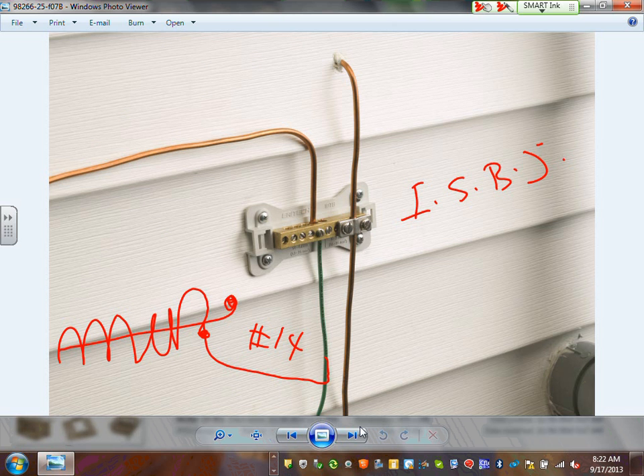It has a space where you can bond the shield. Then you take number 6, and that goes all the way to a ground rod or to the grounding electrode system of your building. This is a requirement for phone and TV for every building. Right by the service, the electrical contractor must install that so-called inter-system bonding jumper for all the low voltage disciplines.